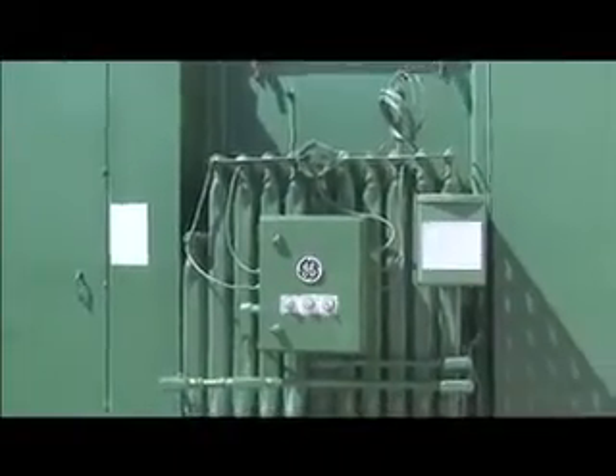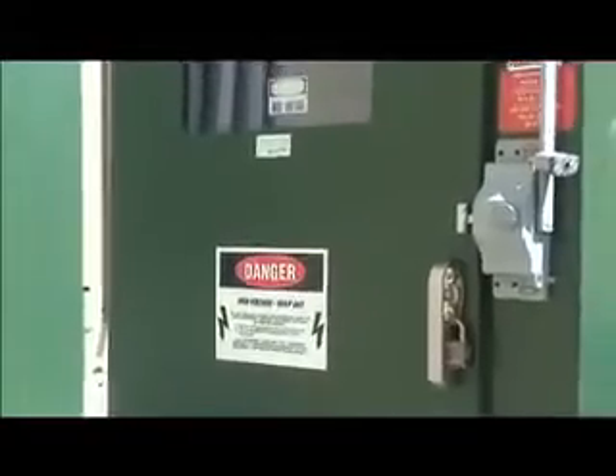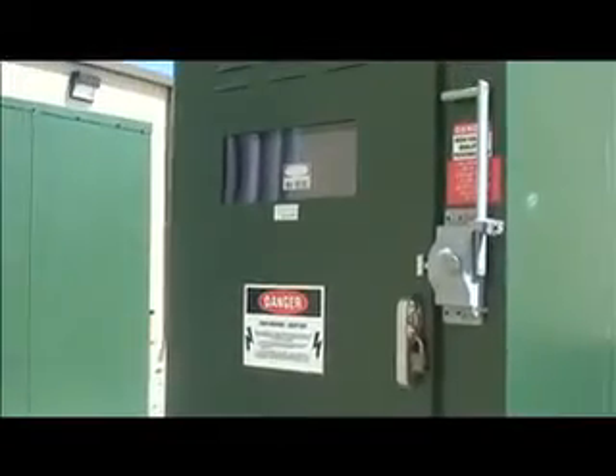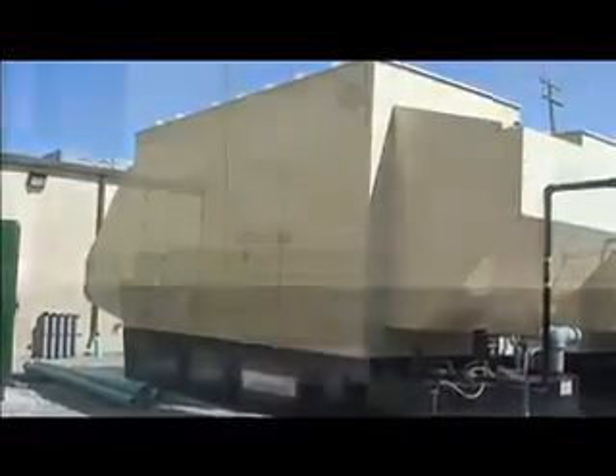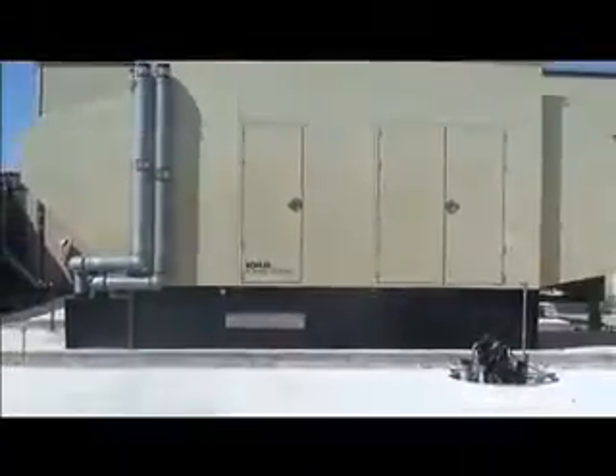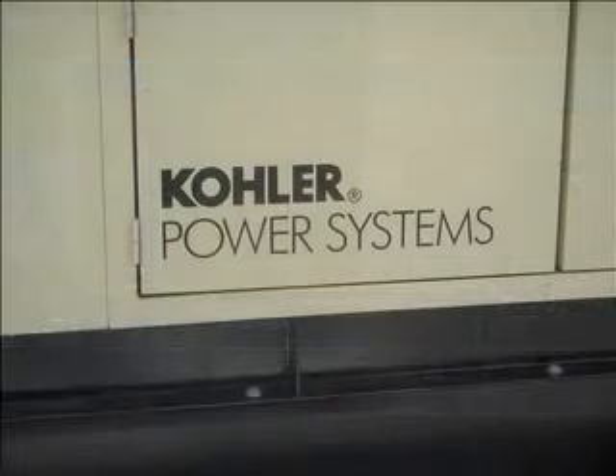Liberty Center 1 is connected to Detroit Edison through our private 2.5 megawatt primary transformer. In the event of a loss of primary power from Detroit Edison, the dual UPS system will carry all customer and critical system load until the dual backup generators come online. We have 20 to 30 minutes of battery time at full data center capacity. These dual generators are rated to start in 20 seconds, but start reliably in 10 to 15 seconds.